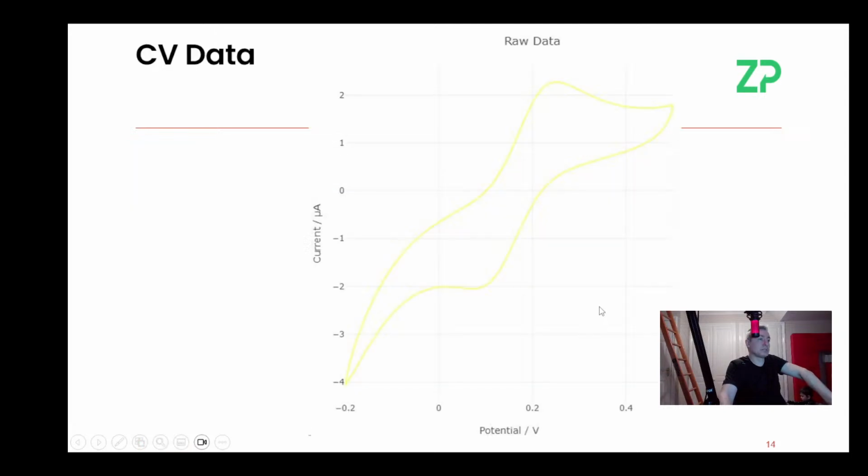Anyway, to the point, we do have all these screen printed electrodes. I think they're really good. This person was asking what's the kind of voltage range that they can use these screen printed electrodes on. When we're testing them in-house, this is a cyclic voltammetry of ferricyanide. We do a lot of testing of these electrodes before they actually leave and go off to our clients. And so we actually test them between minus 0.2 and 0.5 volts.